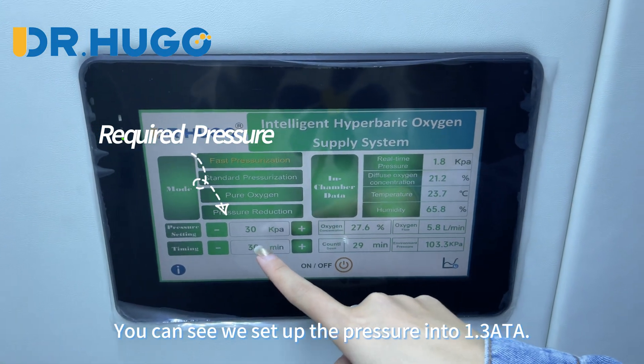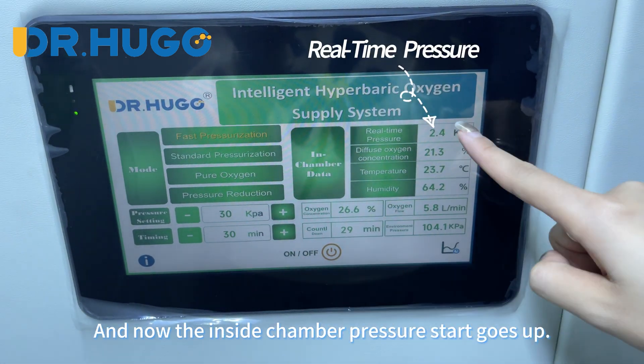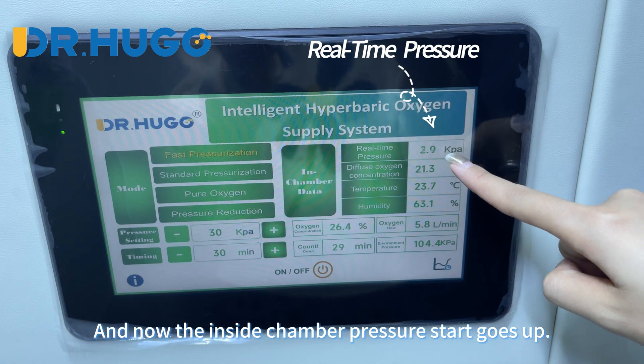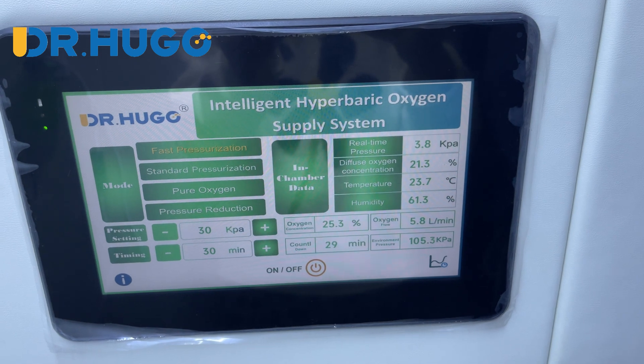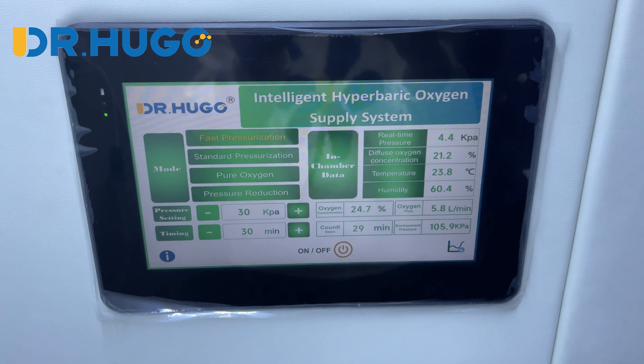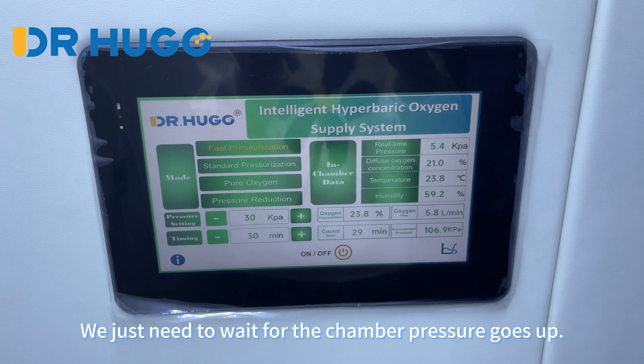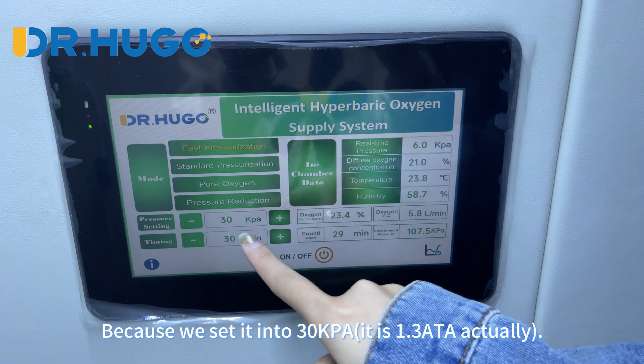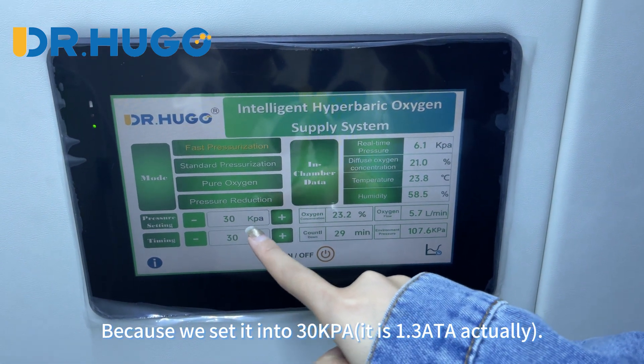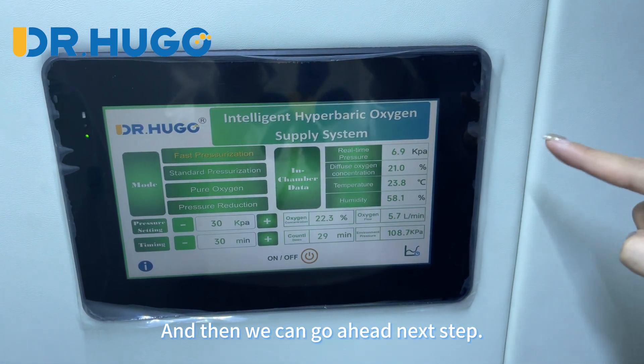You can see we set up the pressure to 1.3 ATA. The inside chamber pressure bar is going up. We just need to wait for the chamber pressure to go up. We set it to 1.3 ATA and just wait for it to reach that level, then we can proceed to the next step.